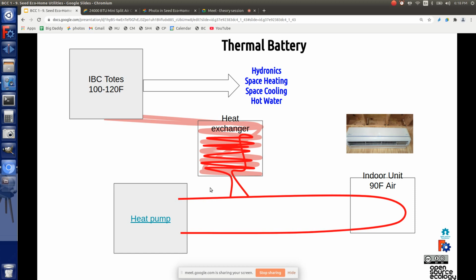So now you take that hot water, so you remove yourself from the heat pump proper, which does only air to air. You're taking heat or cool out of the air, and you're blowing that heat or cool into the air inside the house. But we'd like water because water is a thermal storage medium. Air does not do well for heat storage. It's very low specific heat, how much heat it can embody for a given amount of volume or mass. It's not great. Water is a great heat cool storage medium. So now we're extracting that energy from the heat pump, either hot or cold, into the totes, into the water.